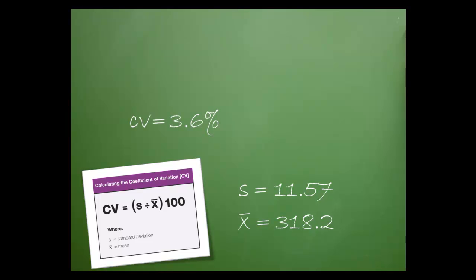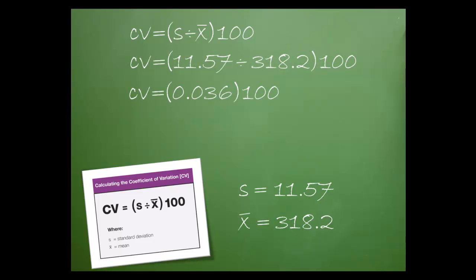The CV is 3.6%. Here's how I got that figure. First, I entered the mean and the SD into the formula. I divided the SD by the mean. The result was 36 thousandths, which was then multiplied by 100. The result was a CV of 3.6%.